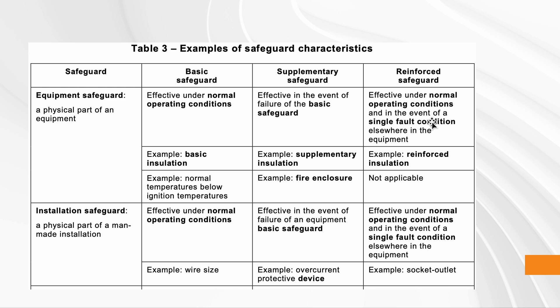Under normal operating conditions and also under single fault conditions, a reinforced safeguard — for example, reinforced insulation — will still be effective. If you cannot have a reinforced safeguard, you might use basic insulation plus supplementary insulation. The standard defines what each of these means. If there is a single fault condition somewhere else, the basic plus supplementary combination might be sufficient to replace the reinforced safeguard.